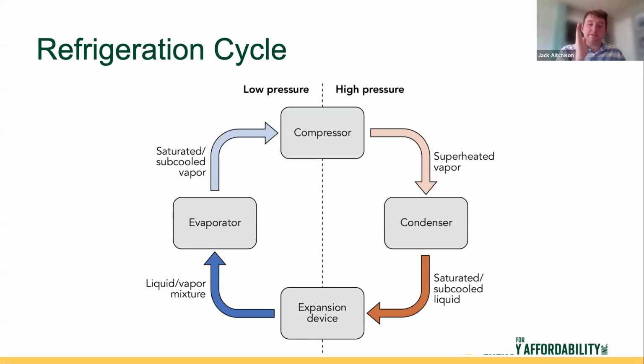See that dotted line, low pressure versus high pressure. Pressure in a refrigerant and really, all substances is synonymous with temperature, right? As the pressure increases, the temperature is going to increase as well. So by going from low pressure through a compression cycle to high pressure, that vapor goes from subcooled vapor to a superheated vapor just through applying pressure to it and pressurizing that vapor.